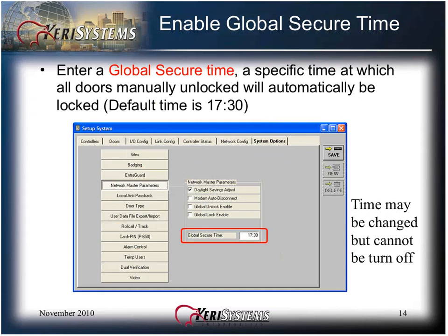Enter a Global Secure Time, which is a specified time at which all doors that were manually unlocked will automatically be locked. The default time is 17:30, or 5:30 PM. The time may be changed but it cannot be turned off.